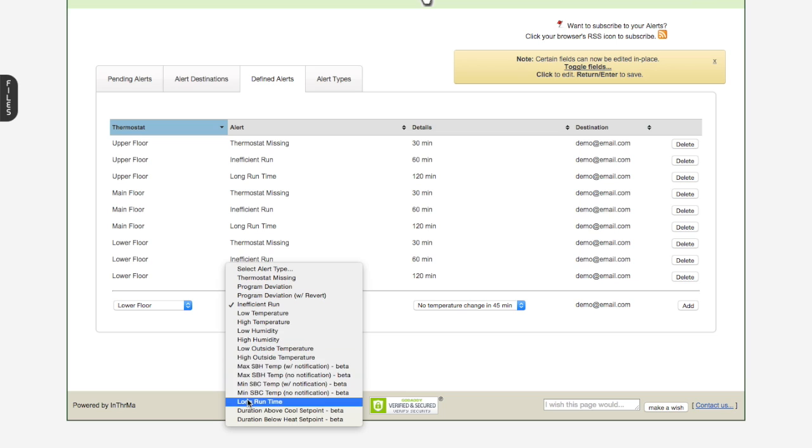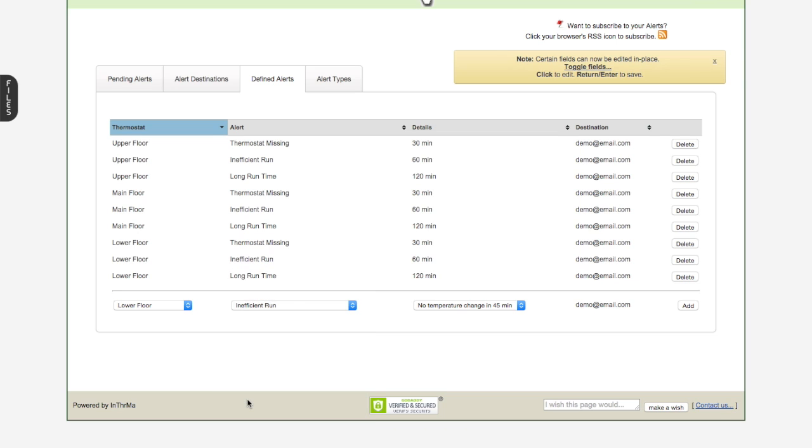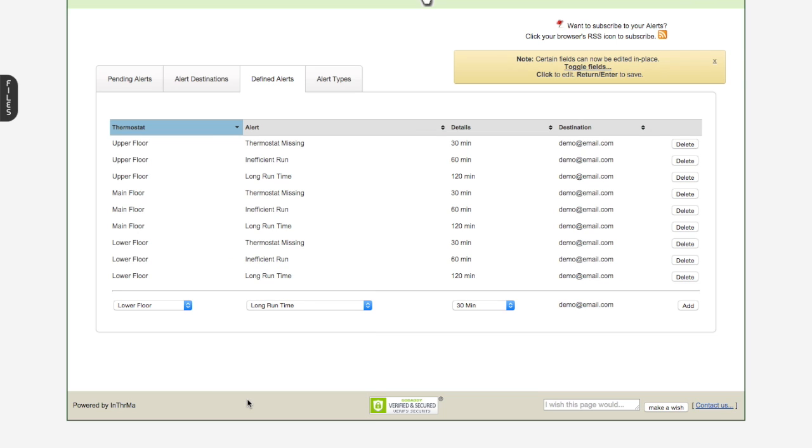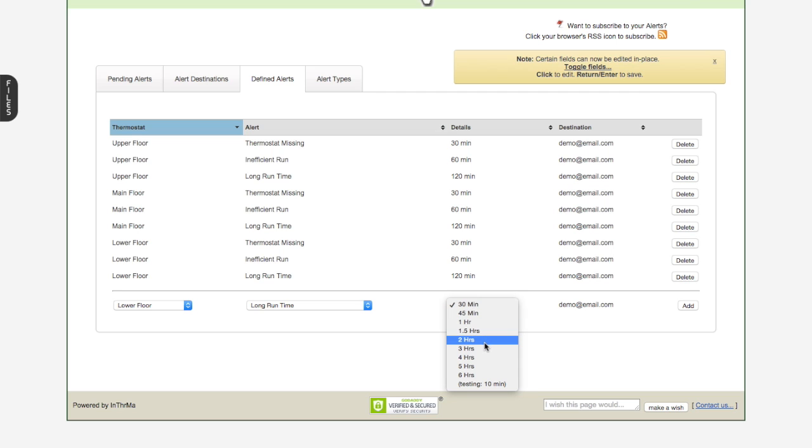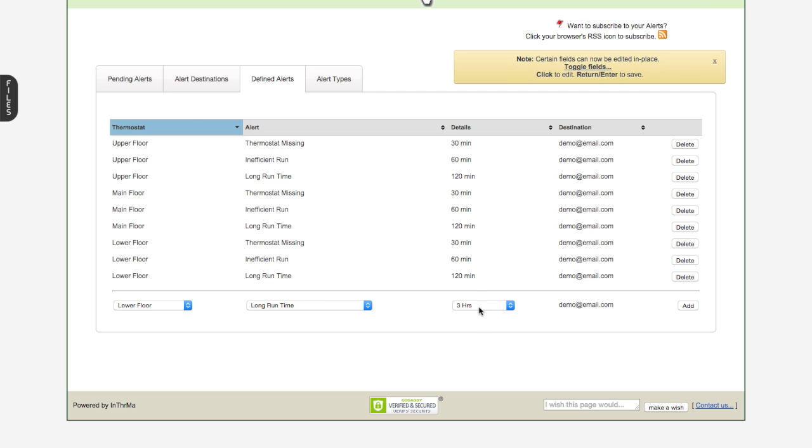The third one that we'll cover on this session here is long run time. So long run time is kind of similar to inefficient run, but it's a little different. So what long run time is, let's set a threshold here, let's say three hours. So if a cooling or heating cycle comes on, and lasts for more than this threshold, in this case three hours, then let me know. And it could be working, it could be working fine, it's just for some reason, it's a long cycle.